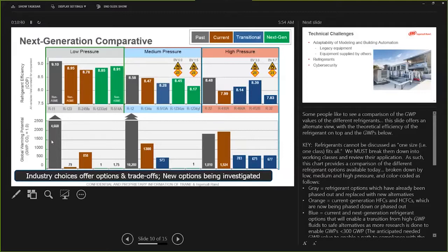The first one here, R11, you can see has a global warming potential very, very high. Ultimately, we're looking for global warming potentials below about 100. So in the lower left-hand part of the chart, you can see what the GWP, or GWP equivalent, of these refrigerants is. The advantage on low pressure is that this discussion has really all but been settled from a technical standpoint. R1233ZD, R514A, provide energy efficiency that's very, very close to the best that we've ever seen, and at the same time have global warming potential that is very, very low, 1 to 1.75 times the potency of carbon dioxide. These are great refrigerants for use in large buildings. Typically, they're used in centrifugal compressor applications.